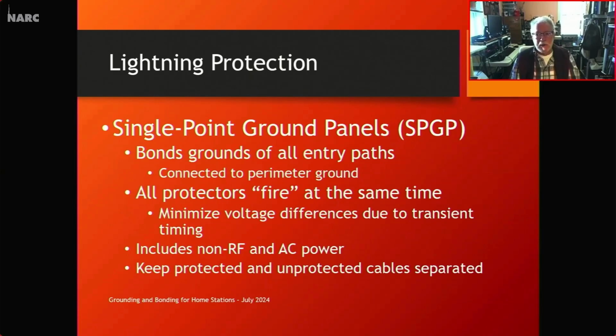This also, the grounding of these protectors on the panel, should include your non-RF and AC power. If you can mount your single point ground panel, sometimes referred to as an entry panel, near the AC service entrance, they've already got an earth electrode there for protection. Bond them together outside, and that helps minimize inductance and keeps the voltages at the same level.